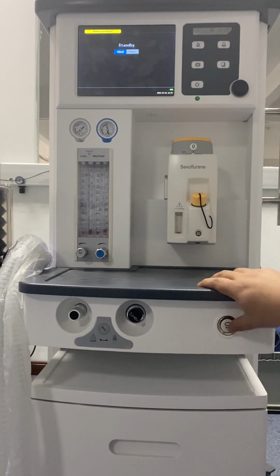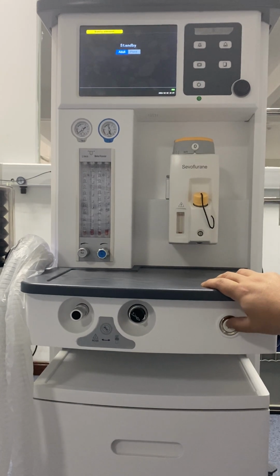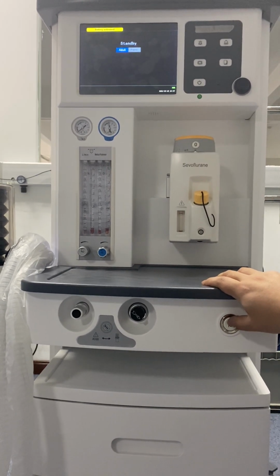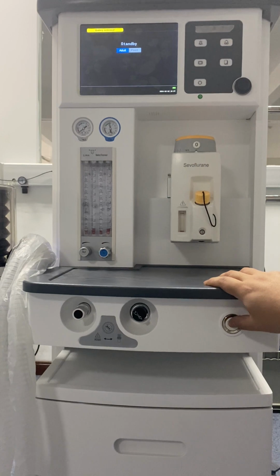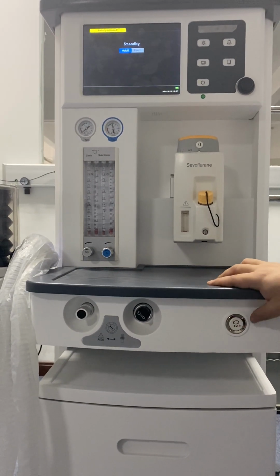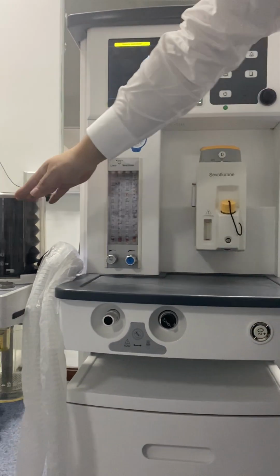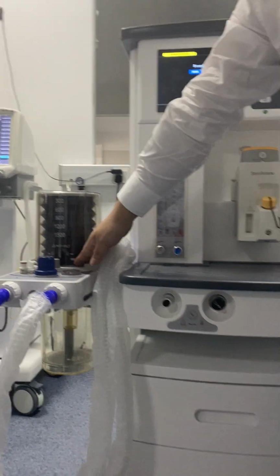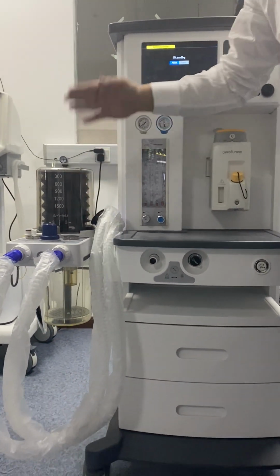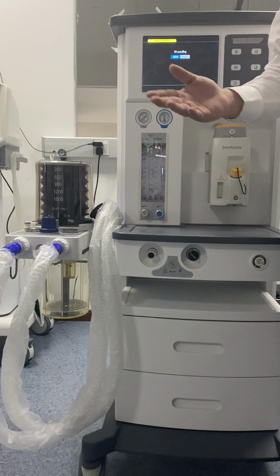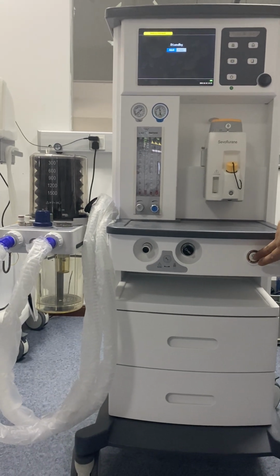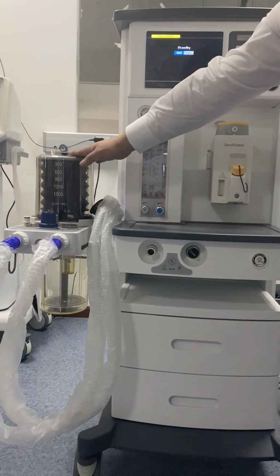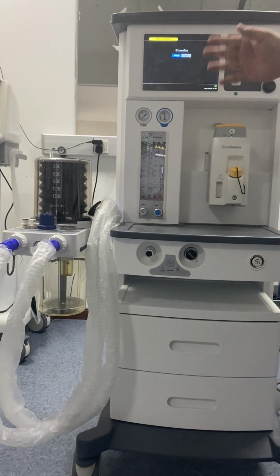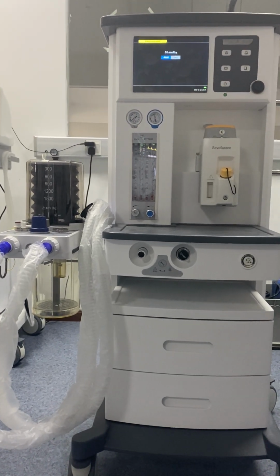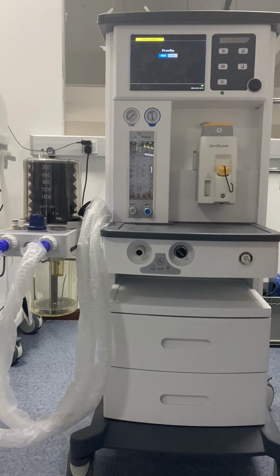The second function is that every time before the operation, after we set all of the ventilation mode and parameters, the bellows will still be at the bottom side. If we want to get into the operation as soon as possible, we can press the rapid oxygen supply to bring the bellows to the top side, and then we can already use the machine. So these are the 2 functions of the rapid oxygen supply button.